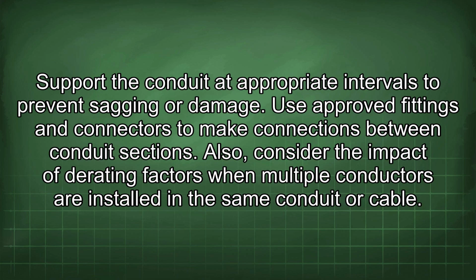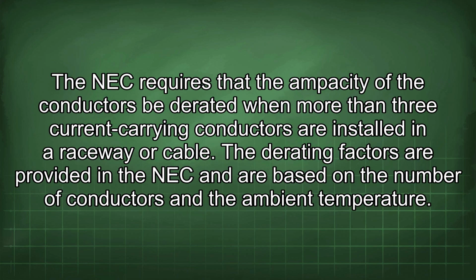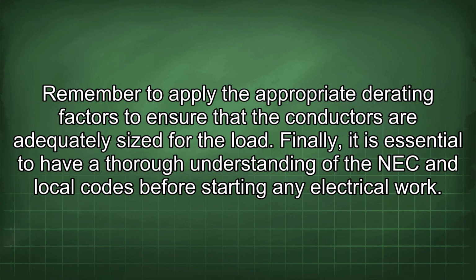Also, consider the impact of derating factors when multiple conductors are installed in the same conduit or cable. The NEC requires that the ampacity of the conductors be derated when more than 3 current-carrying conductors are installed in a raceway or cable. The derating factors are provided in the NEC and are based on the number of conductors and the ambient temperature. Remember to apply the appropriate derating factors to ensure that the conductors are adequately sized for the load.